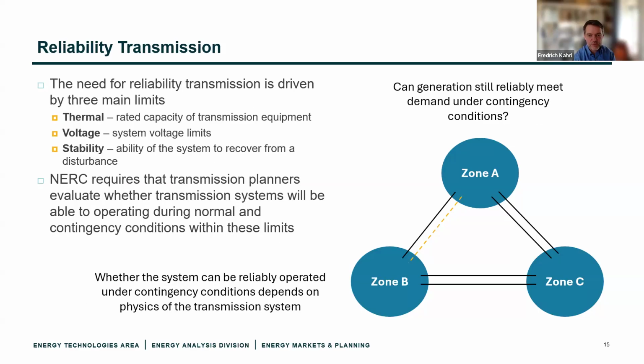Because power flow changes once a line goes out, or in some cases once a generator goes out, we have to use power flow models to figure out: if we lose this line or these generators, are we still able to maintain reliable operations? A lot of transmission planning is dedicated to this question - we take transmission lines out one at a time, or sometimes in tandem, and see whether the transmission system can still operate reliably.